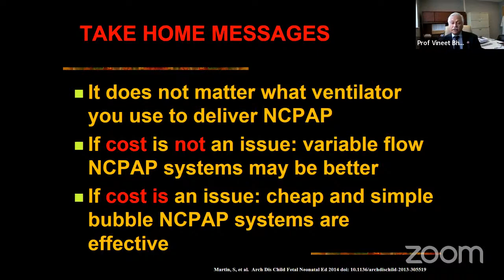CPAP pressures, I tend to avoid more than 8 centimeters. I know there are units in Australia, for example, maybe some in Europe, that are using higher. But personally, I am concerned. I'm sure you're aware of the COIN trial. I'm sure you're aware of the increased incidence of pneumothorax. And I know the explanation said it's probably not because of the high pressures, but I find, especially for the bigger babies, that if I use higher pressures, I have seen enough air leaks that I tend to avoid it.